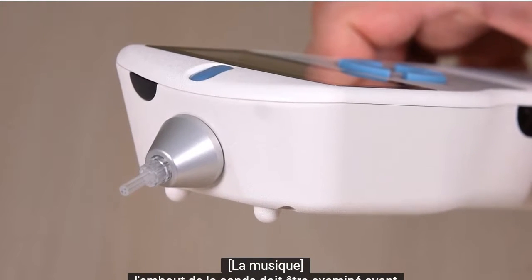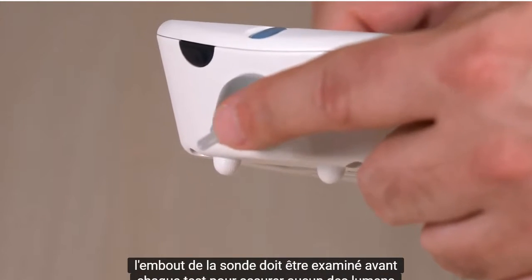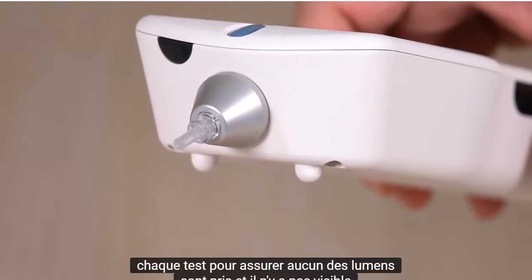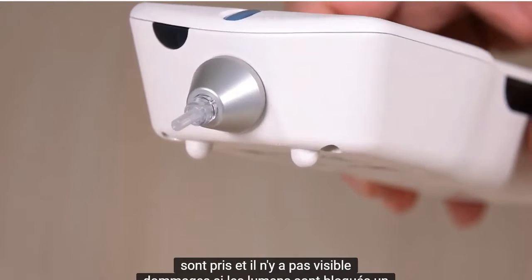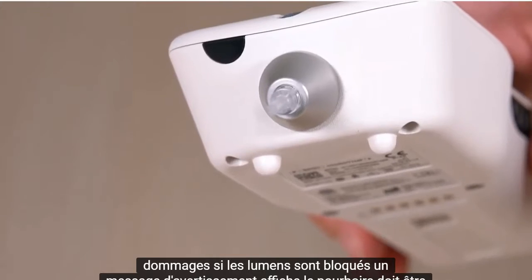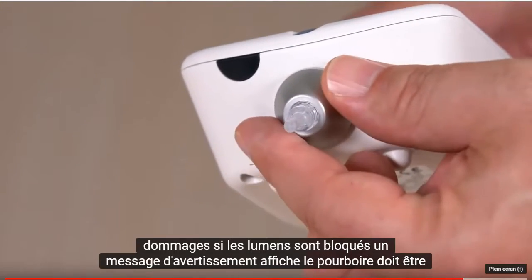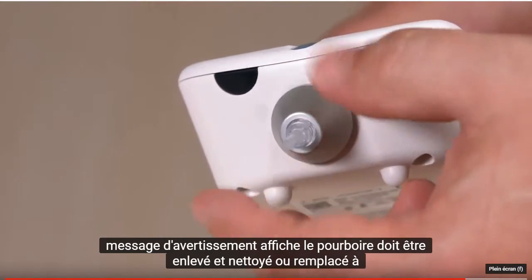The probe tip should be examined before each test to ensure none of the lumens are blocked and there is no visible damage. If the lumens are blocked, a warning message displays. The tip must be removed and cleaned or replaced.